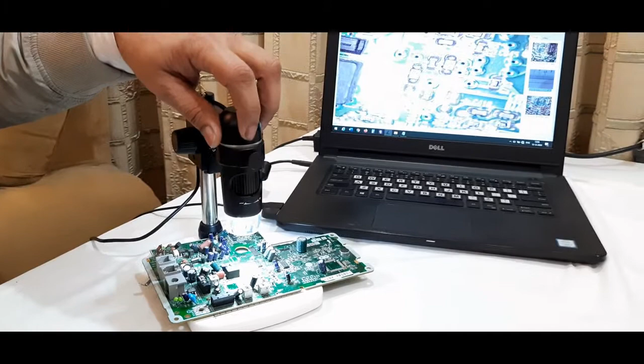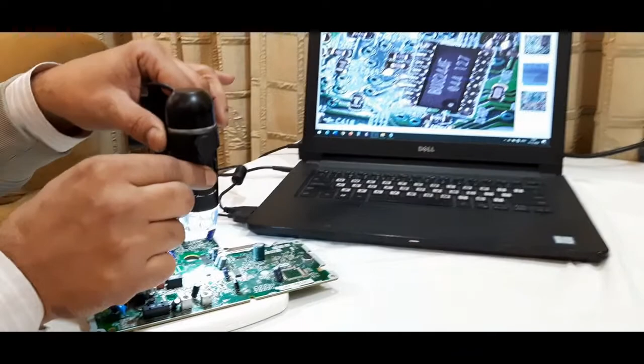Right now, the image is live on the screen, and there's a knob on this microscope, as you can see, which by rotating clockwise we can decrease the intensity, and by rotating anti-clockwise we can increase the intensity of LEDs. So you can adjust the light intensity according to your application, and there is a knob also on this microscope for focusing. By rotating it anti-clockwise we can decrease the magnification, and by rotating it clockwise we can increase the magnification. So adjust the knob accordingly to focus on the object you want to inspect, as we are doing here.